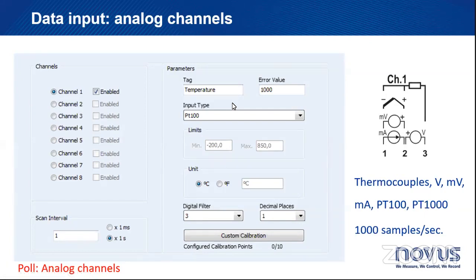Tag is the name of the channel. This is what is going to be displayed when you download data from the FieldLogger. Error value is basically what will show up both on the screen and also on the reports in case your sensor fails. So if I have a thermocouple connected directly to the FieldLogger and by any chance one wire escapes or my thermocouple is blown away, what happens is the error value is going to be displayed on the screen and also recorded in the memory. One thing that is important here is you can also create an alarm for when error value happens, so you will be notified if any sensor goes to error value. So that is a possibility, okay?